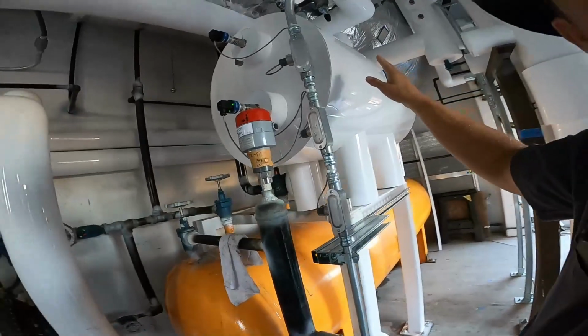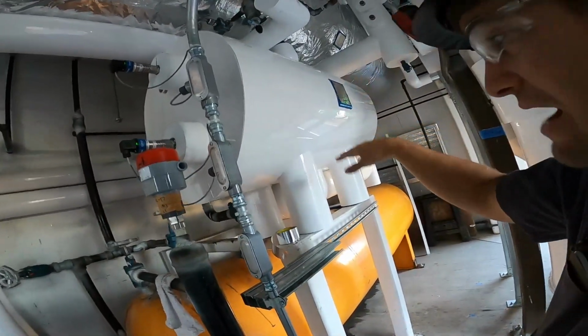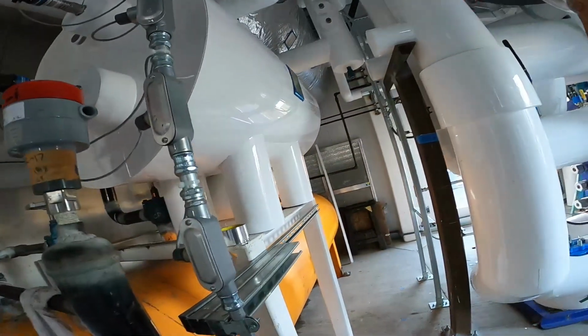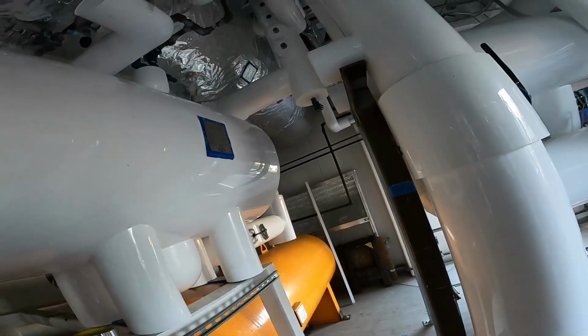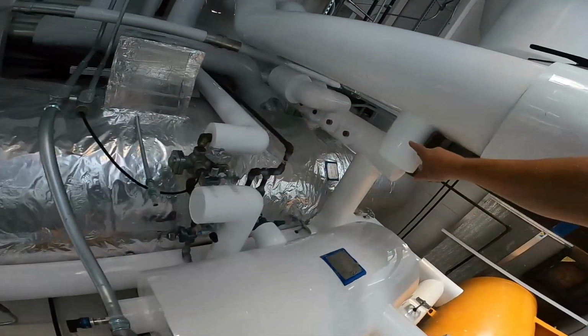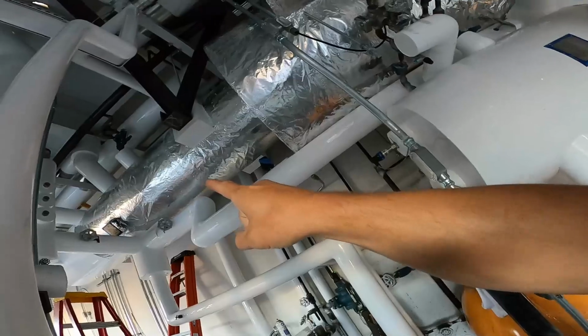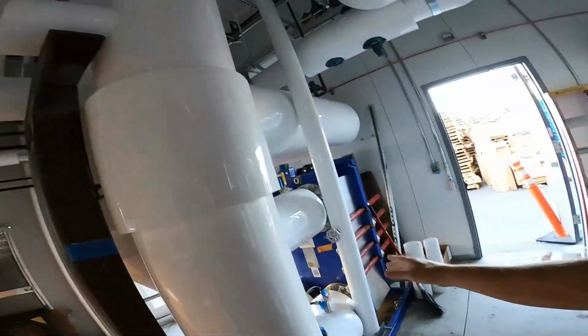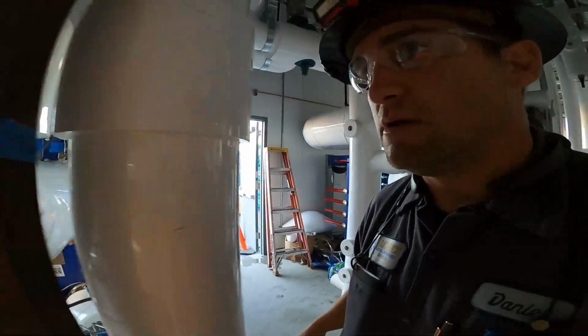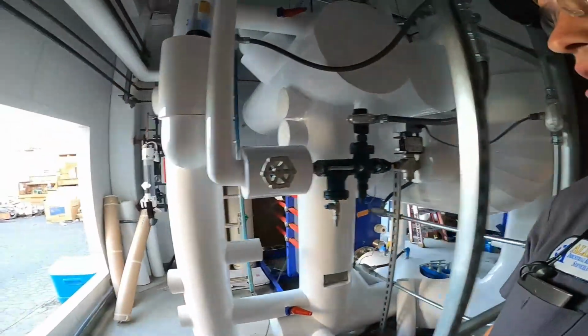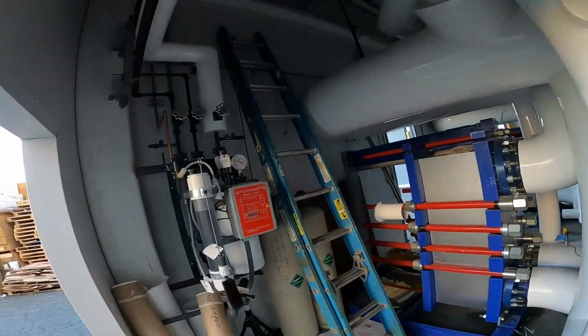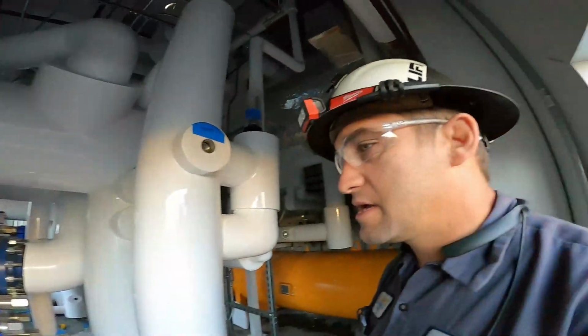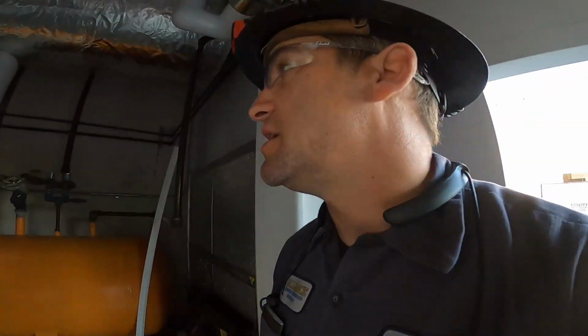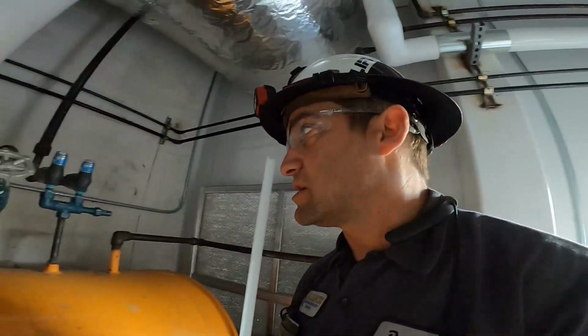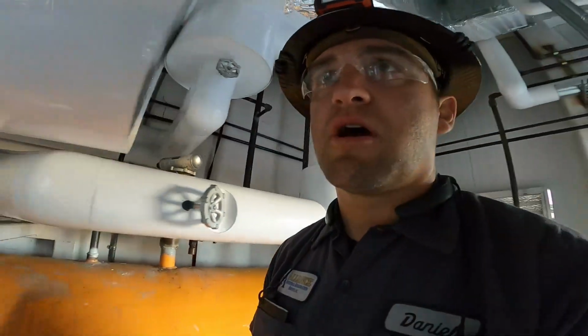It is a gravity drain, so this will gravity drain into the high pressure receiver. Here's our low temperature accumulator, medium temp accumulator, heat exchanger 1, heat exchanger 2, and our auto purger. So the auto purger is off right now because the system's off. So it does shut down when the system's off. And make sure you guys do that when you're putting your auto purger in.